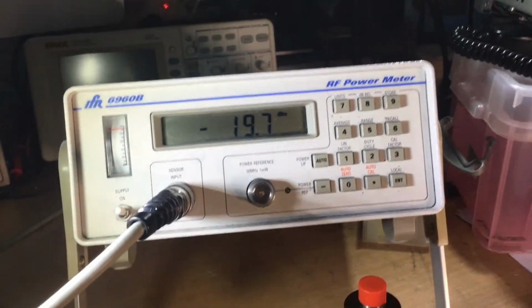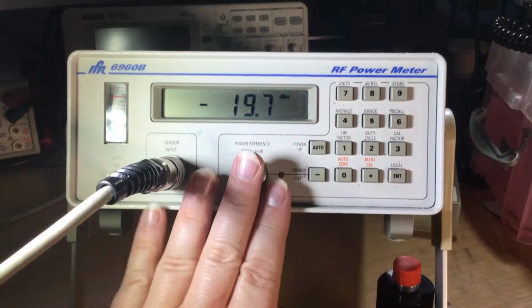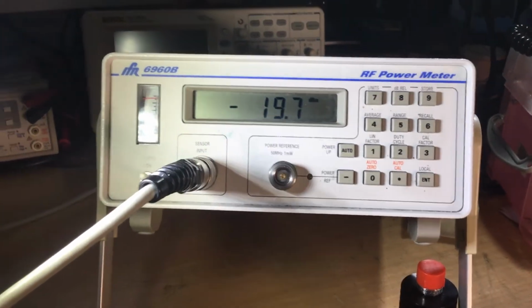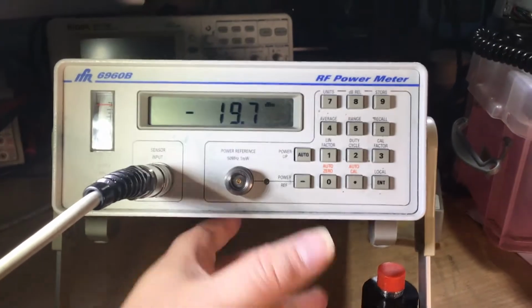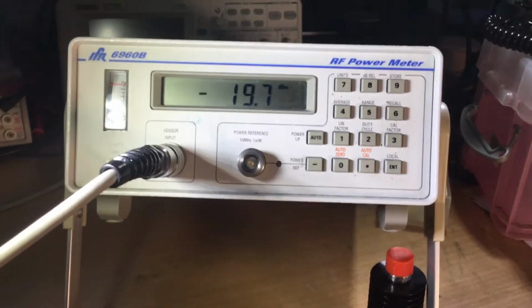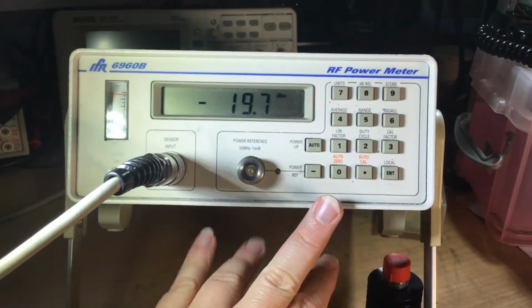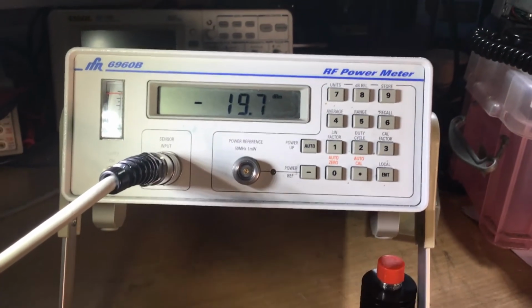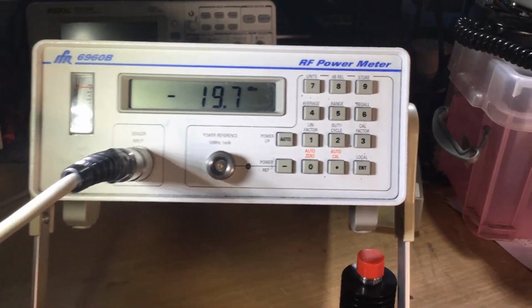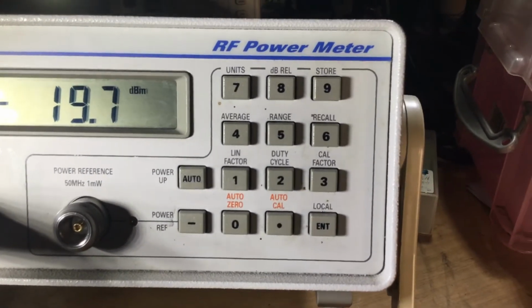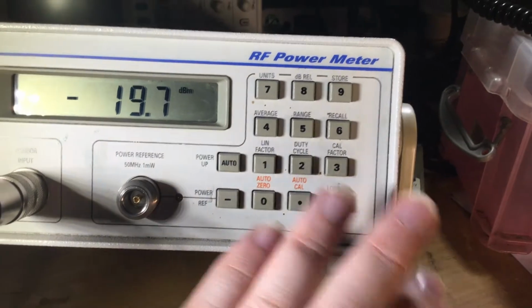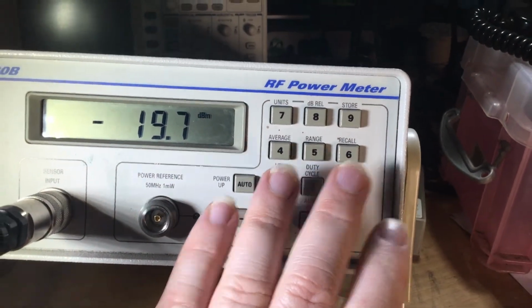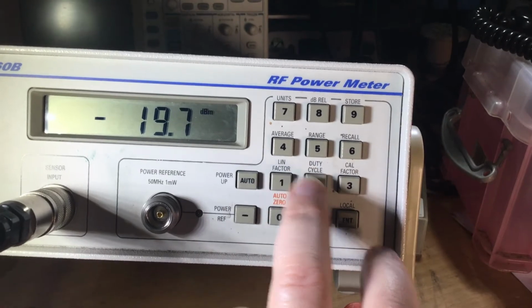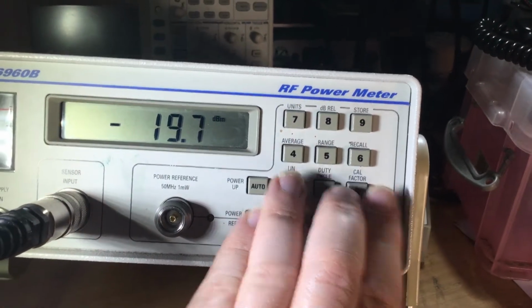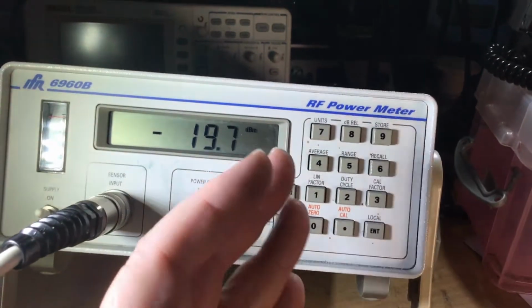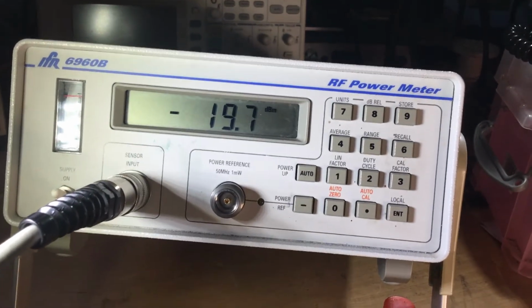So that's a particular usefulness of this instrument, plus as well, the microwave test set uses that as a benefit. So these are quite useful for doing calibration work, for measuring pulse signals, CW signals, etc., in conjunction with the 30 dB attenuator. You would need to enter in the data for very precise measurements, like I've done here, the linearity, duty cycle and Cal Factor data that's written on the side of the sensor. Otherwise it won't read accurately.